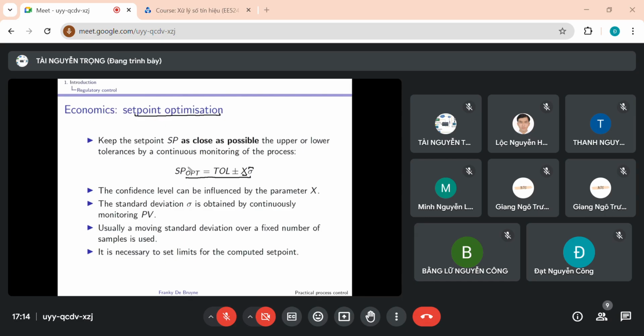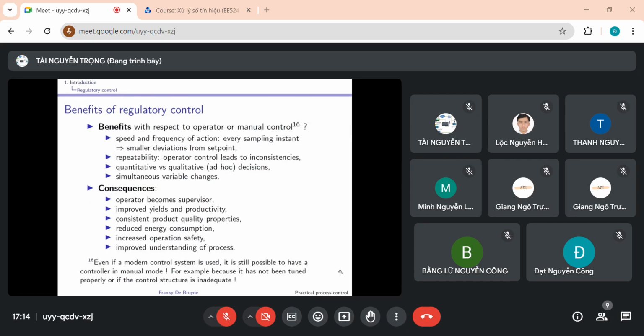Of course, if you do such a thing, you have to implement measures so that this computation of the optimal set points can be done in a safe fashion. For instance, that there is a maximum and minimum value and that there is some gradient that is imposed. There are, of course, a number of benefits when you compare process control in automatic mode to manual control. The speed and frequency of action is better. So every sampling instant you have a new MV that is computed, so the variations in MV will be smaller and also the deviations from set point will be smaller.